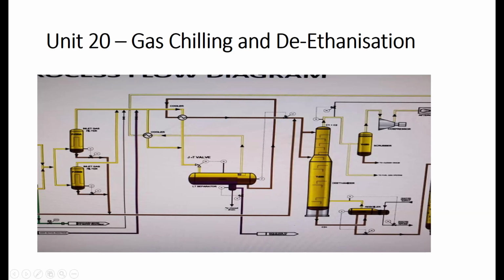Within this temperature, chilling and warming, if you do not dose glycol, it is paramount that you dose some form of adsorption process, so that any entrained water molecules are absorbed. Glycol as a chemical has a very high affinity for water, so it will absorb the water, and when it does, it will have a higher density, and hence it will be at the bottom of this separator.